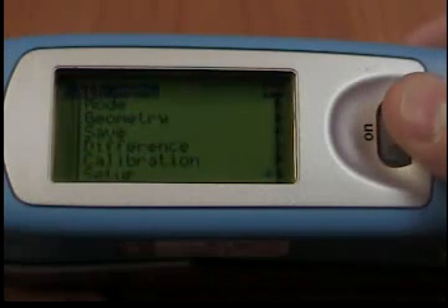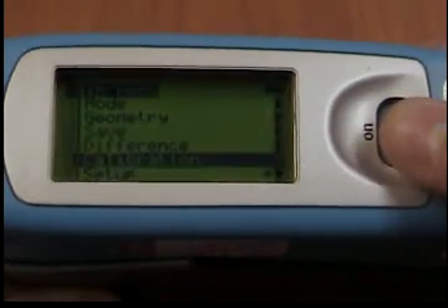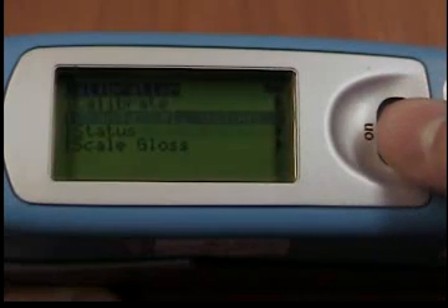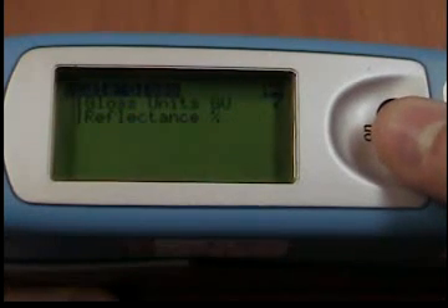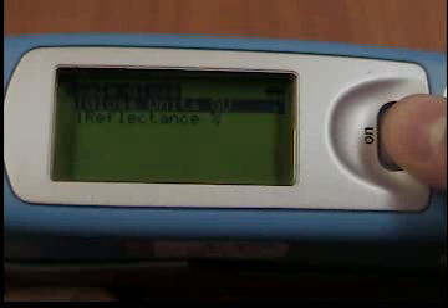Scale. You can use the Scale menu option to switch back and forth between gloss units and reflectance. Move the mark to the desired entry and press Mode. A check mark identifies the scale that is selected. After you switch the scale, the unit must not be recalibrated.